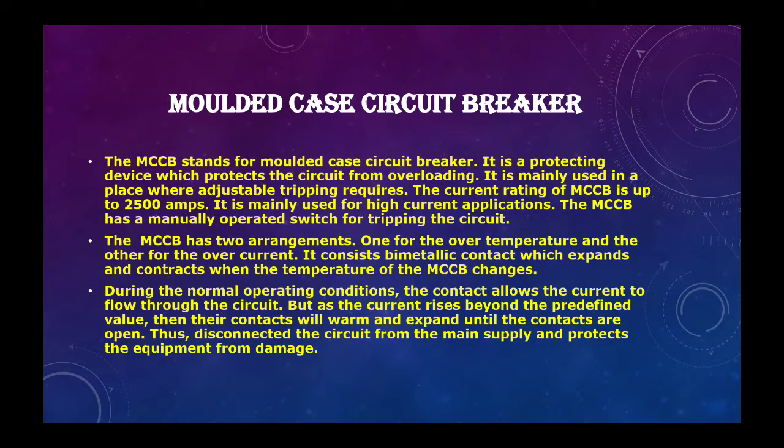During normal operating conditions, the contacts allow the current to flow through the circuit, but as the current rises beyond the predefined value, the contacts will warm and expand until the contacts are open. Thus, the circuit is disconnected from the main supply and the equipment is protected from damage due to overloading.